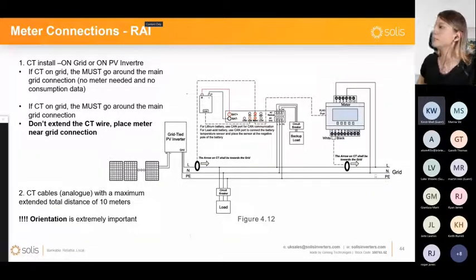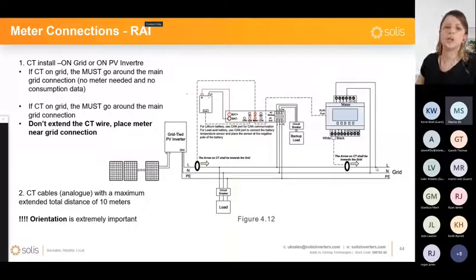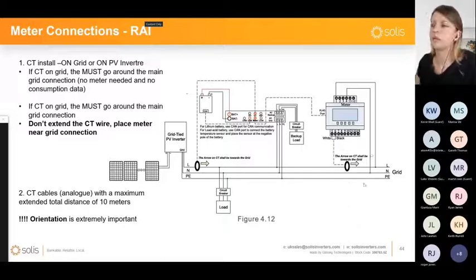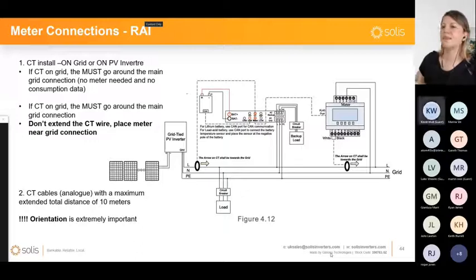I think Kevin has a question. Yes, hiya, Carmen. Just a quick question. So the power to the meter, the live on terminal 1 and the neutral on terminal 4, does that have to come from the PV circuit, or can it be from a separate circuit? No, it can be from a separate circuit without any problems. What is very important is where the CT clamp is installed, and the placement of that CT clamp needs to be on the main AC connection point. But from where you get the power supply, the voltage probably will not vary too much anyway, and you only have one line, so the power should be calculated correctly. Perfect, thank you. Okay, you're very welcome.